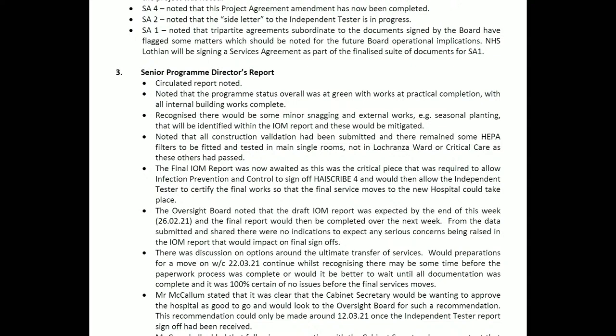Reading down below, it's noted that all construction validation had been submitted and there remained some HEPA filters to be fitted and tested in main single rooms, not in Lochranza ward or critical care, as these others had passed. The final IOM report was now awaited, as this was the critical piece required to allow infection prevention and control to sign off, and would then allow the independent tester to certify the final works so that the final service moves to the new hospital could take place.